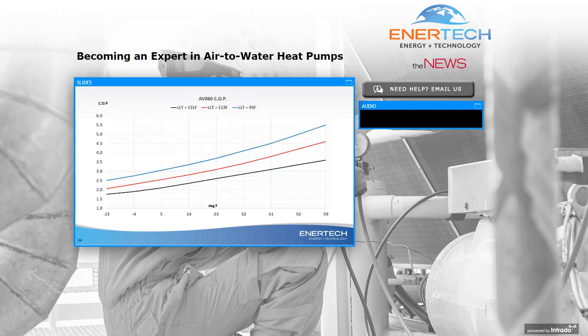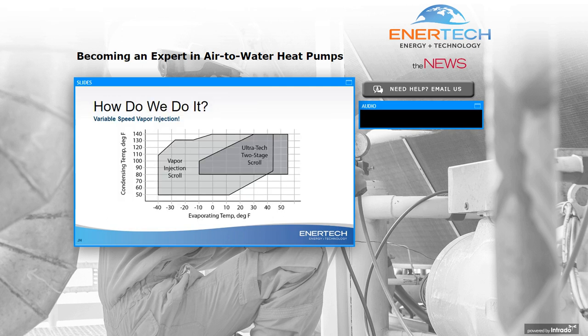So this is its companion chart. You can see the blue line is our typical radiant floor curve, which might even be higher if we can go less than 95 degrees with outdoor temperature reset, which I'll talk about here shortly. If we're doing domestic hot water, then we're probably looking at that black line. But even with domestic hot water, you can see the COP is somewhere around 1.8 at its coldest temperature where it's going to operate. And those are the things we can talk about when we're looking specifically at design applications for this product.